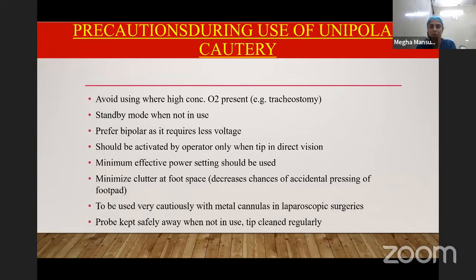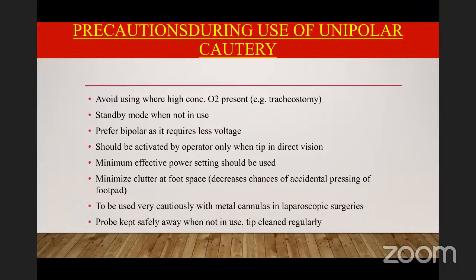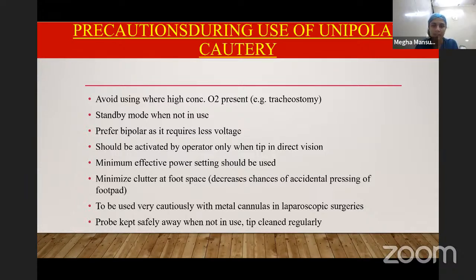We should be using certain precautions during use of electrical equipment to avoid giving shock. We should avoid using it where high concentration of oxygen is present, for example tracheostomy. We should put it in standby mode when it is not in use. We should prefer bipolar cautery as it requires lower voltage. We should prefer that it be activated by an operator only when the tip is in direct vision. It should not be activated if the tip is not in direct vision.